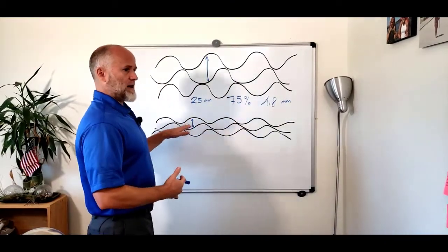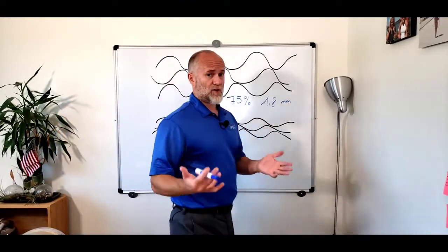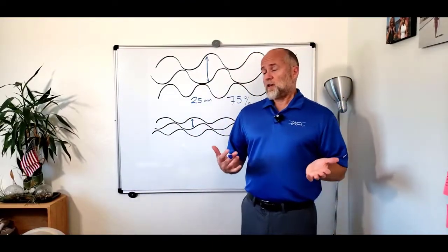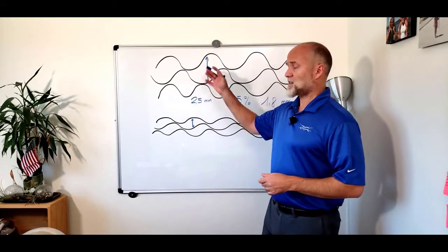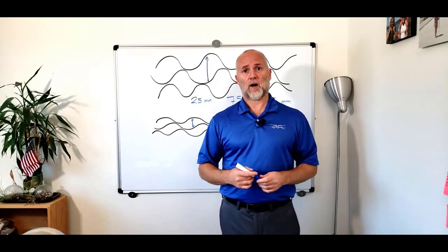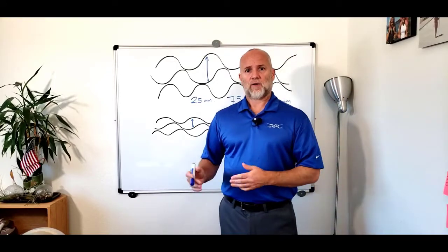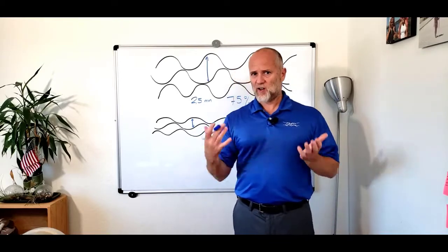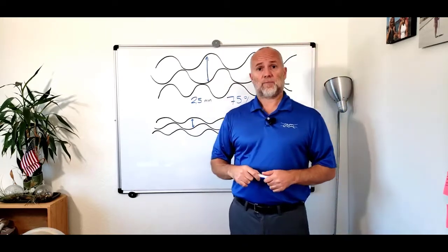And the same goes for here. Let's say that in this case, for instance, this is 1.5 millimeters. You need to design your mesh in the strainer for particles that are around 1 millimeter. Unfortunately, as providers of heat exchangers, we are not asked very often what is the size of the channels, and therefore we see in strainers filters with meshes that are like 4 millimeters. In that case, of course, you screen out the washers, the bolts and the nuts, the gloves, all these very large debris, but the finer particles end up building up in the heat exchanger.